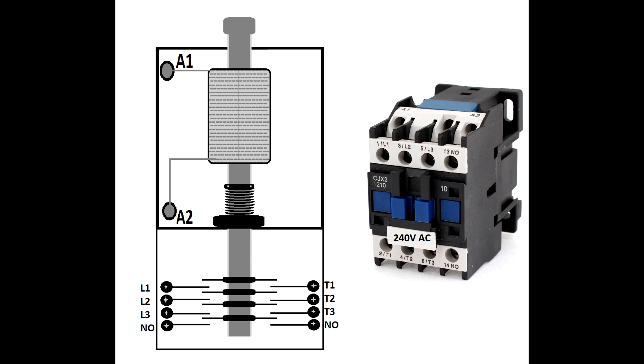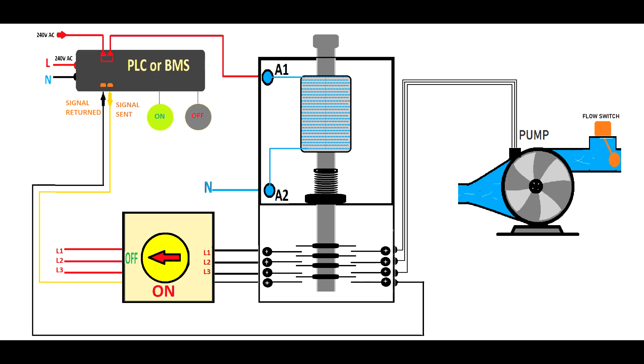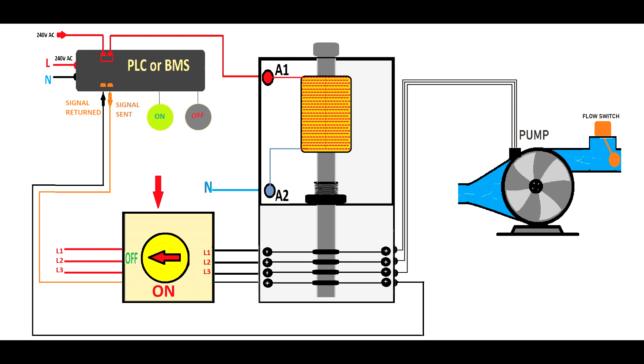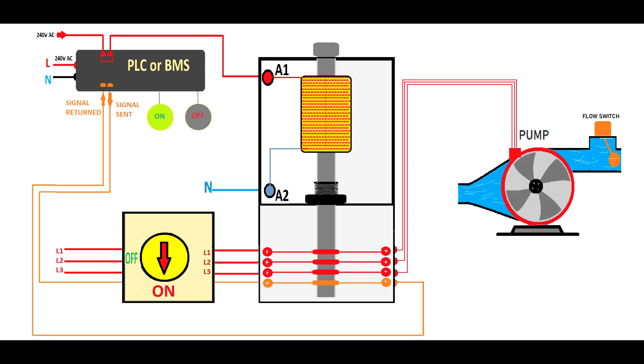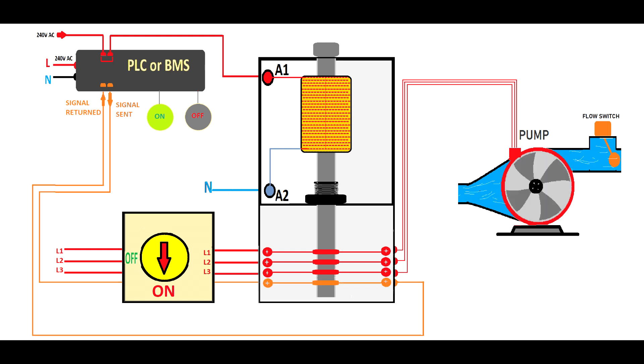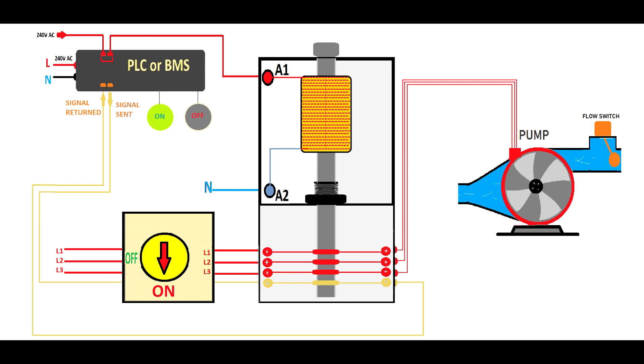This is how the contactor looks: you have a control circuit and a power circuit. As you will see in this picture, you have a programmable logic controller or a building management controller — it can even be a printed circuit board — and the signal is returned through the contactor. The BMS or PLC sends the signal through the isolating switch, it passes to the contactor and returns. This is actually a very bad installation, and I will explain why: if you trace this yellow-orange signal, you will see that the BMS sends the signal through the isolating switch to the contactor, but technically it does not come back.